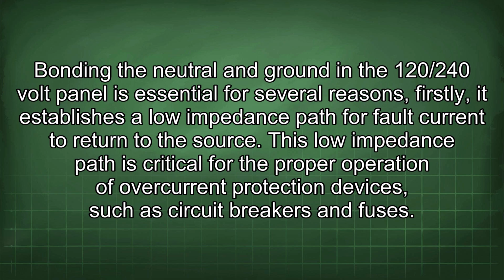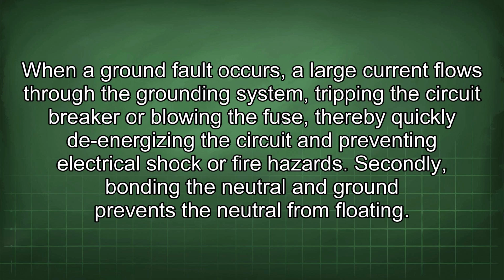Bonding the neutral and ground in a 120/240 volt panel is essential for several reasons. Firstly, it establishes a low impedance path for fault current to return to the source. This low impedance path is critical for the proper operation of overcurrent protection devices, such as circuit breakers and fuses. When a ground fault occurs, a large current flows through the grounding system, tripping the circuit breaker or blowing the fuse, thereby quickly de-energizing the circuit and preventing electrical shock or fire hazards.